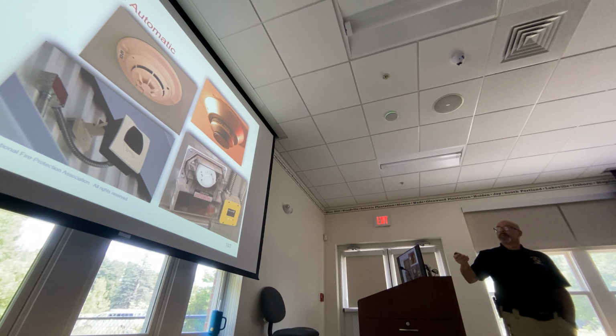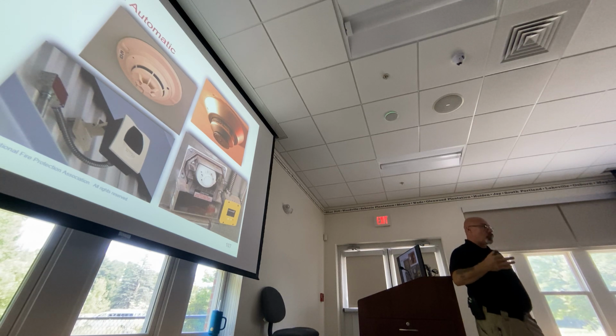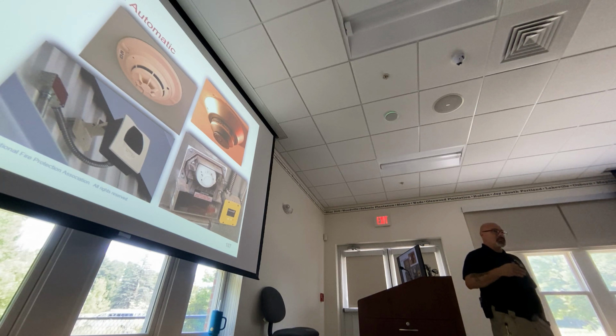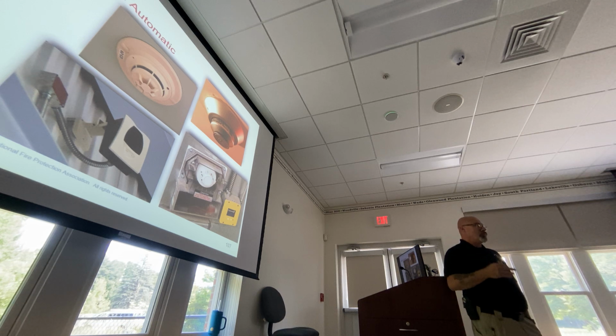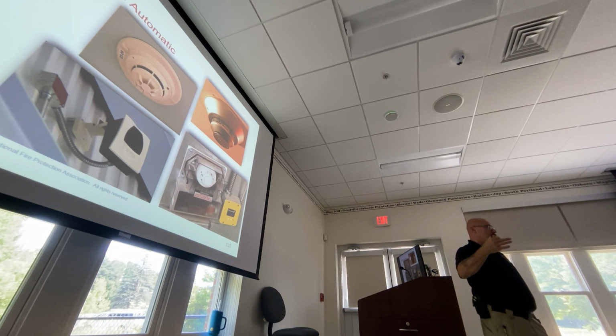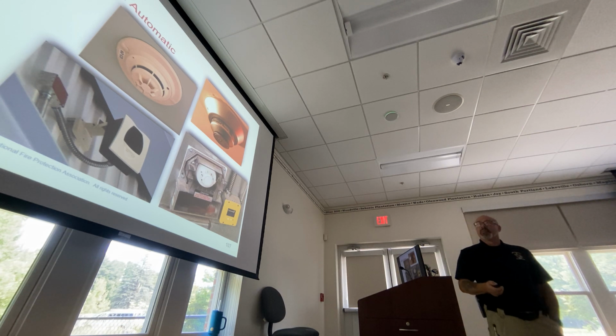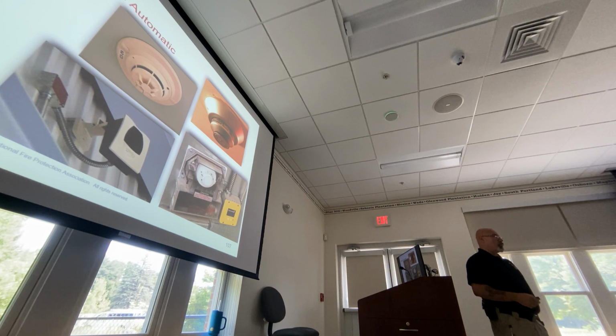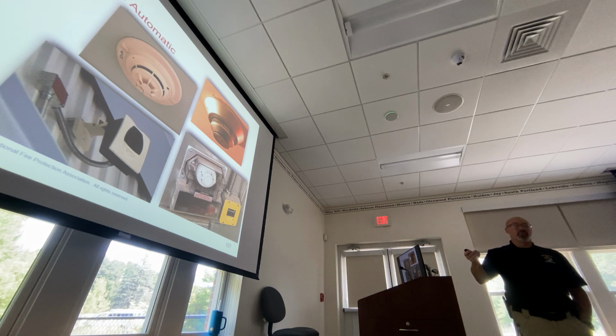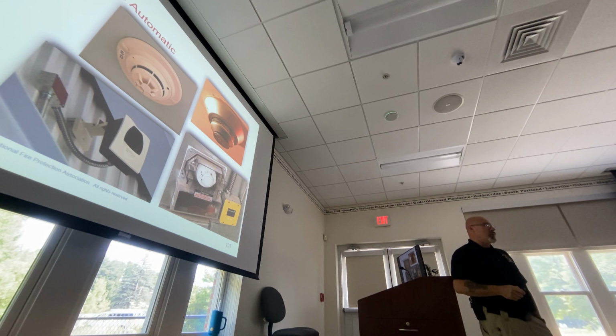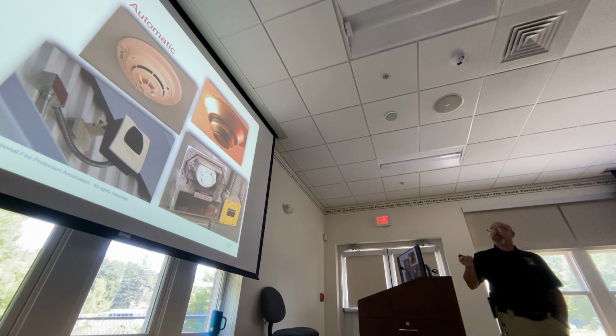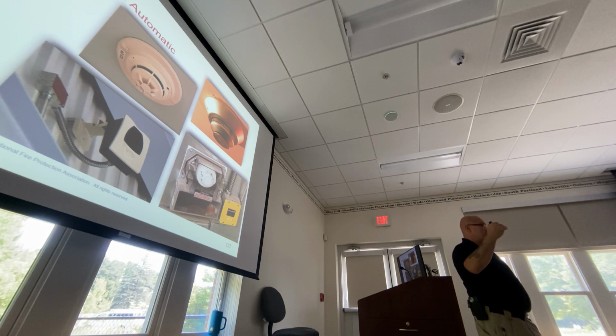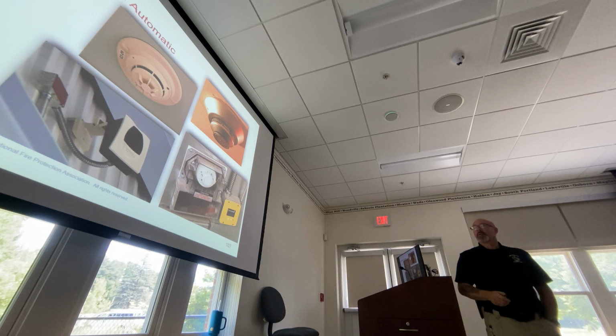Some of these are resettable or restorable. Those are important terms: rate of rise, and restorable or resettable. Some of them are non-restorable, meaning they're disposable. If the temperature goes up and they go into alarm, they get replaced. The resettable ones, once the temperature comes down, either reset themselves or have to be reset. Okay?